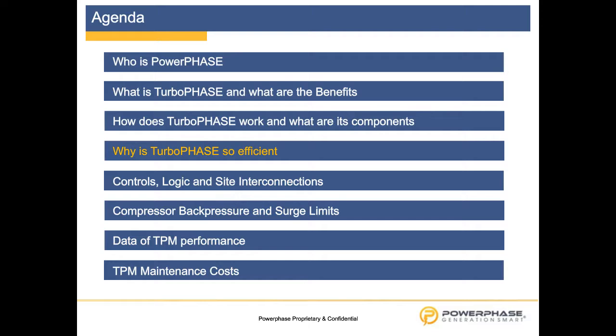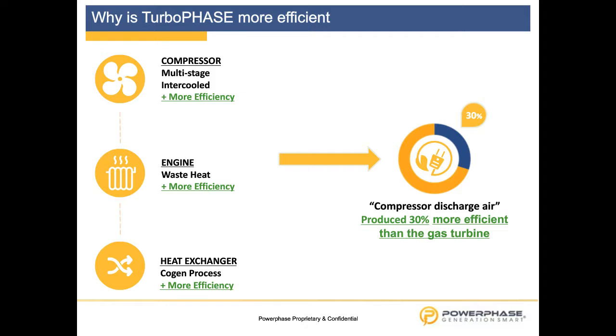Going back to the agenda, the next point was: why is it efficient, and why does it provide fuel savings? So what is this module? The module has a multi-stage intercooled compressor, highly efficient. It has a reciprocating engine that produces heat, and we use this waste heat to heat up the compressed air to the required parameters with a heat exchanger. So what we see here is a small combined cycle where we use the waste heat, and with that we compress the air about 30% more efficiently than the gas turbine compressor does.